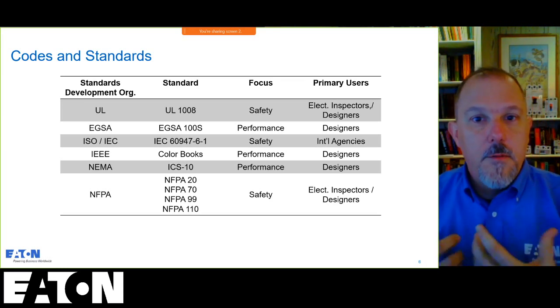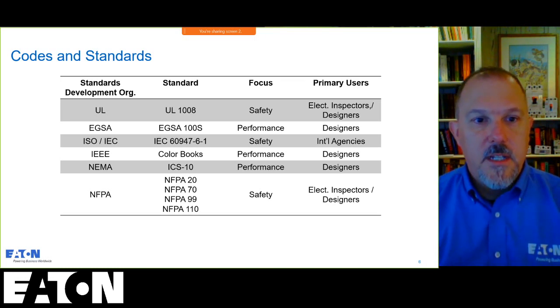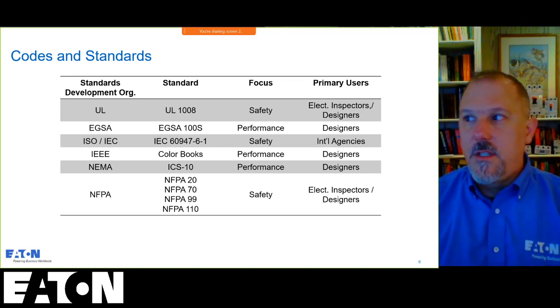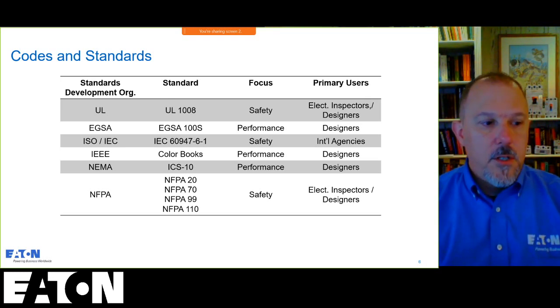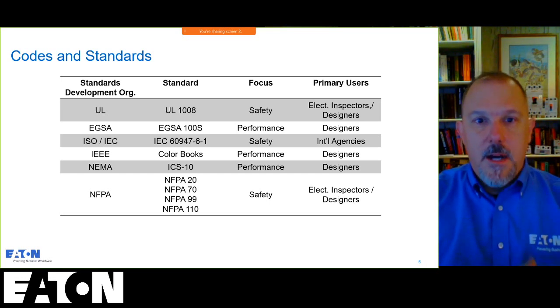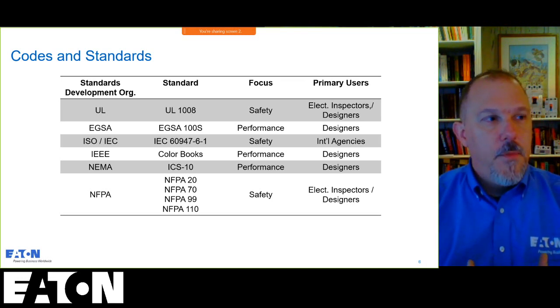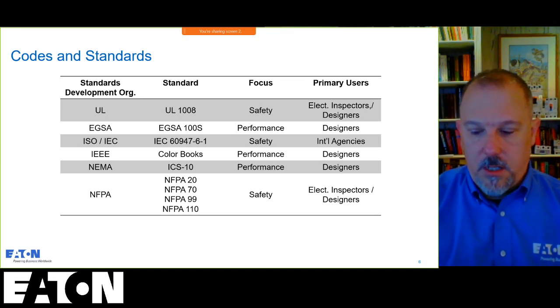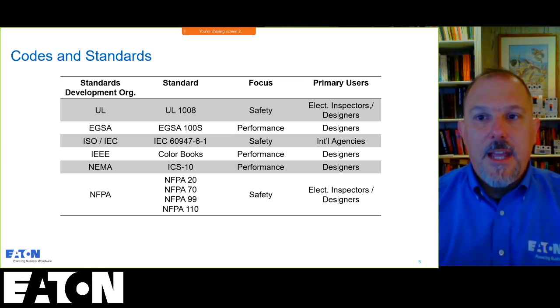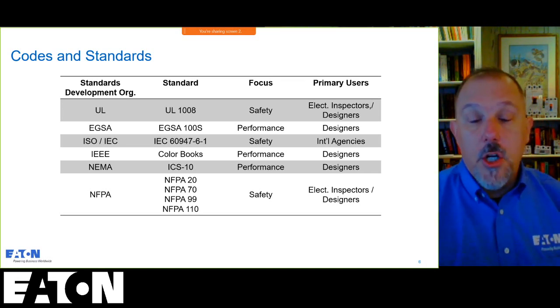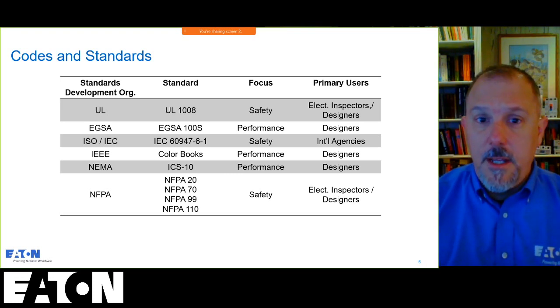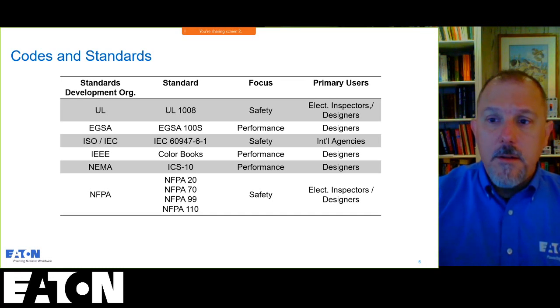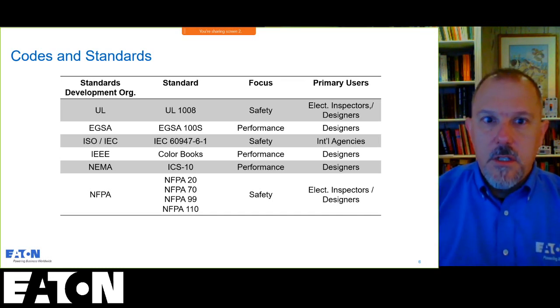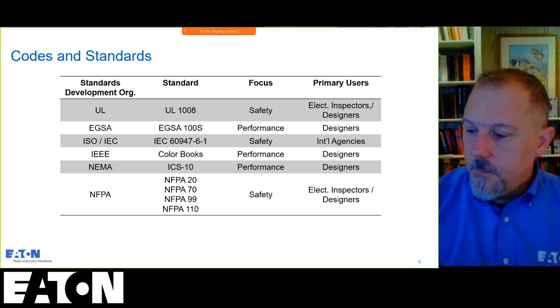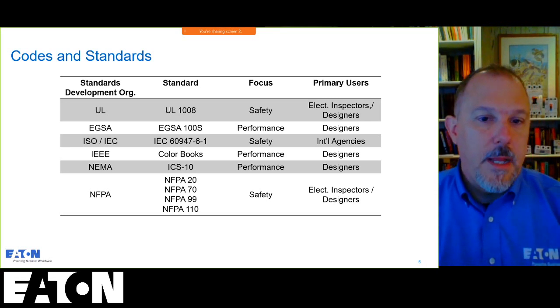A lot of those books are used by designers to help establish performance requirements around power distribution systems. And remember, if you're talking about generators, there are code requirements, which we will talk a lot about, National Electrical Code requirements. But a lot of what drives the application of generators is not necessarily what the code is telling you. It's the reliability that the end user wants out of the power distribution system, whether you're at home and you want that, or you're in an industrial facility where you say it's not legally required, it's not a life safety issue for me, it's all about dollars and cents, making sure I don't go down and my production is still in play.